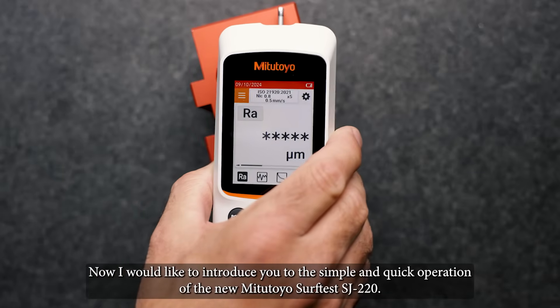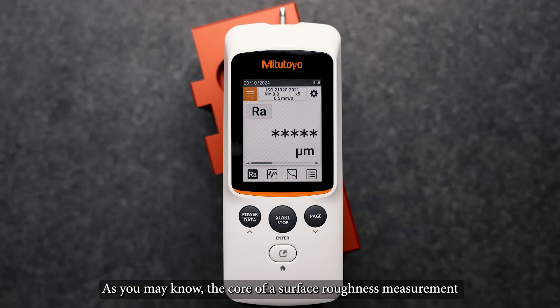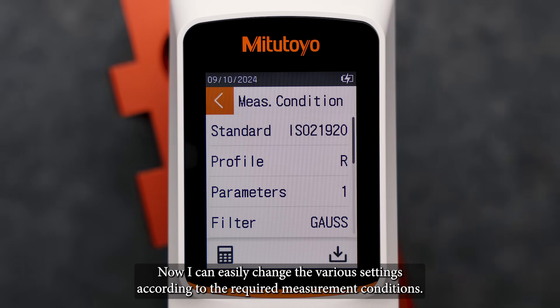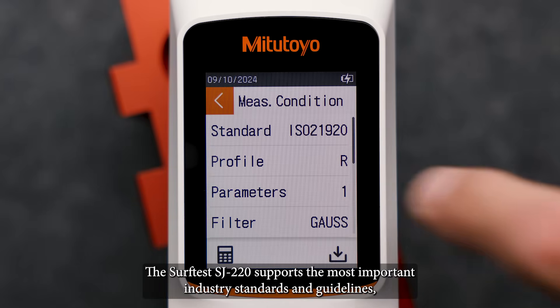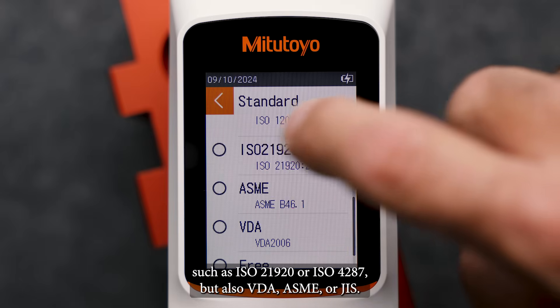Now I would like to introduce you to the simple and quick operation of the new Mitutoyo SurfTest SJ220. The core of a surface roughness measurement lies in the correct selection of the measuring conditions. I open the measurement conditions menu by pressing the upper touch screen display. I can easily change the various settings according to the required measurement conditions. First, we define the standard. The SurfTest SJ220 supports the most important industrial standards and guidelines, such as ISO 21920 or ISO 4287, but also VDA, ASME, or JIS. For this measurement, we choose the ISO 21920 standard.